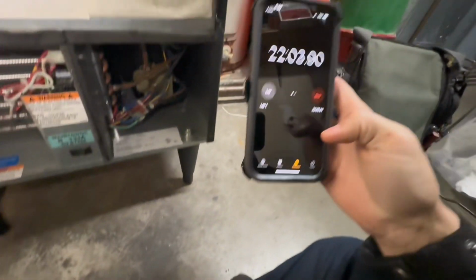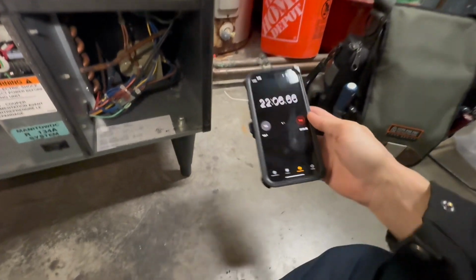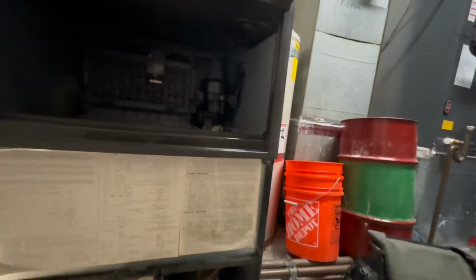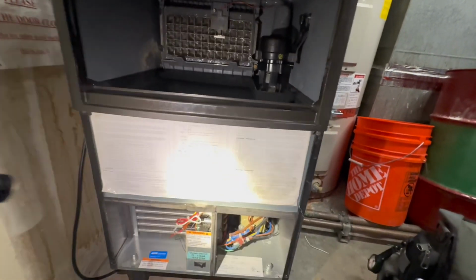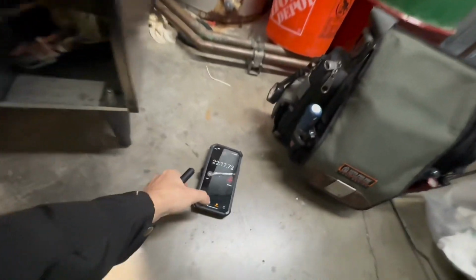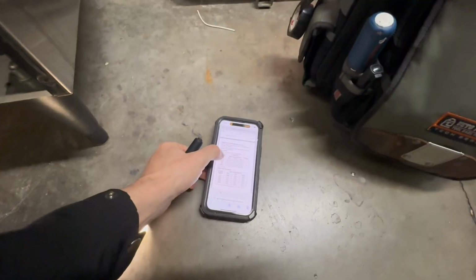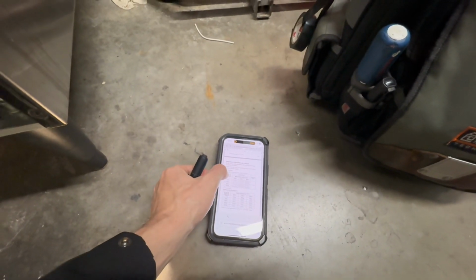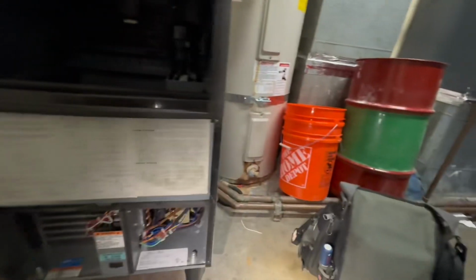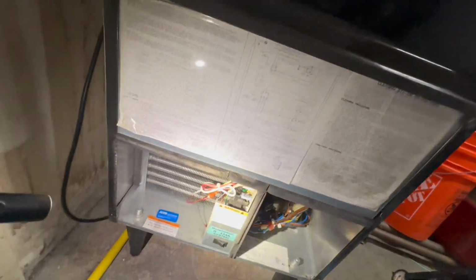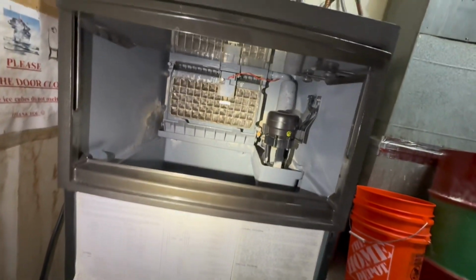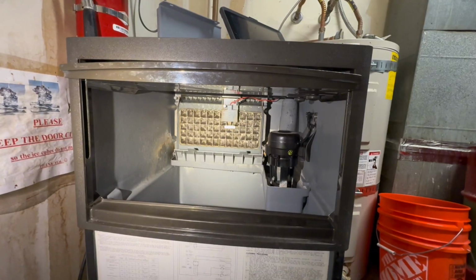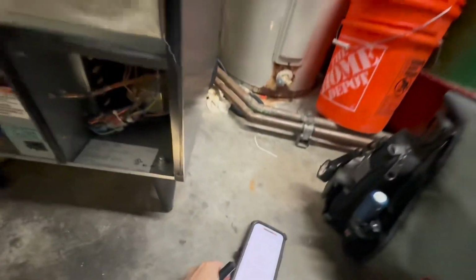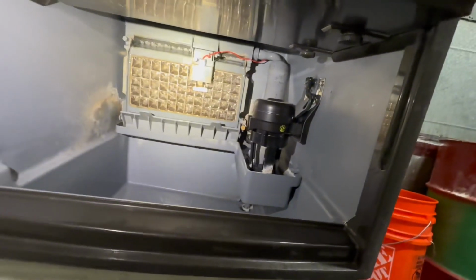So my freeze time so far is 22 minutes. In the manual it says 17 to 21, but because it's the first cycle, it actually has a note somewhere. I don't remember where I read it. I think it's in the manual that first, what does it say? The first cycle at any temperature will take up to 3 minutes longer. So I'm not upset at 22 minutes right now, and any second now we'll go into harvest. All right, we just cycled into harvest. I'm gonna hit my lap, see what happens with this.